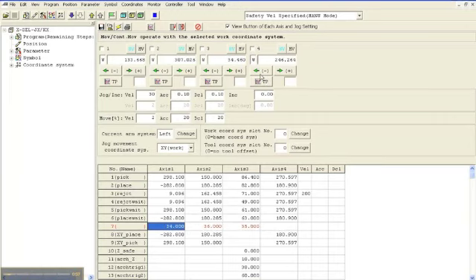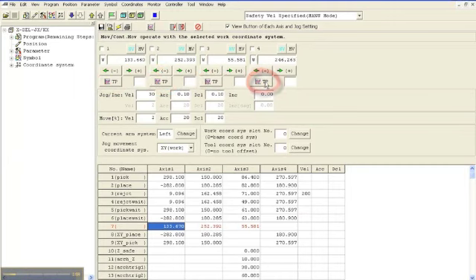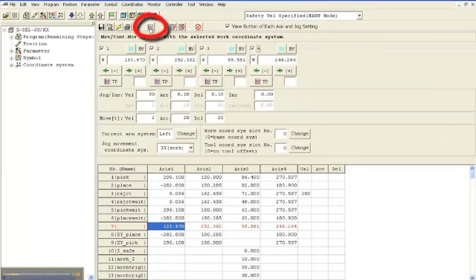The second method is to turn the servos on and jog the actuator to the location that you want to teach. Once you have the actuator in the correct location, you can teach the information one of two different ways. There is a Teach Current Position button under each axis. When you press this button, it will grab the current location of that axis and store it inside the position table. The second method is to click the check box next to each axis that you would like to teach. When the boxes are selected, you can press the Teach All button at the top of the screen.